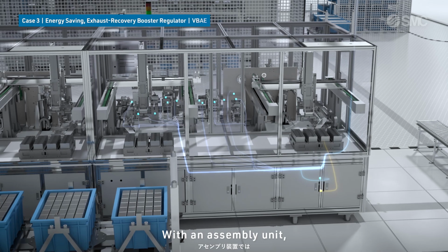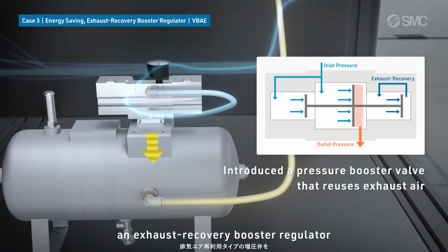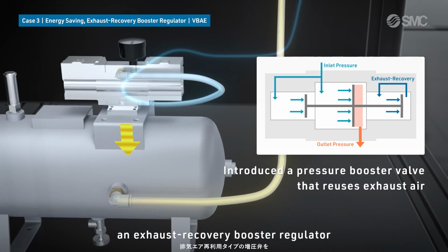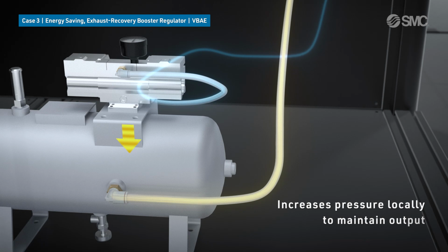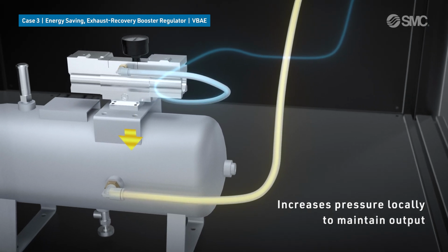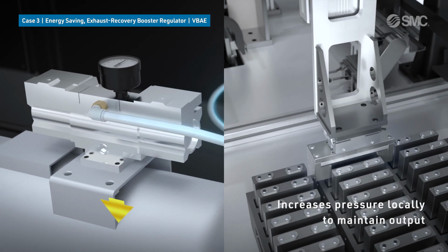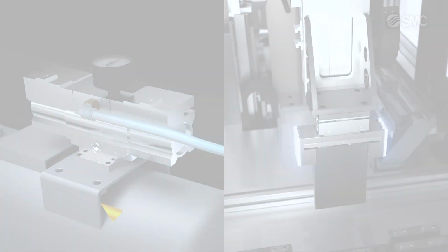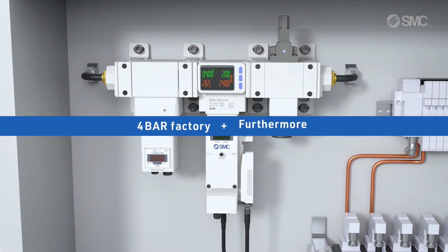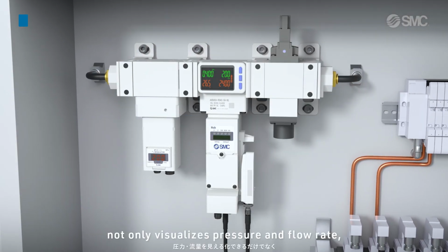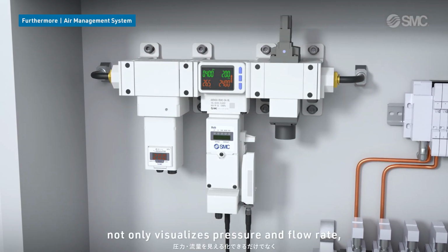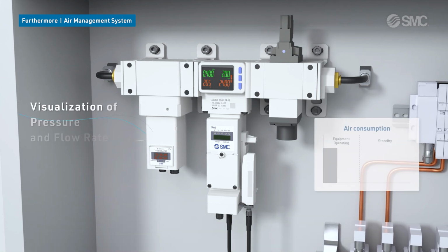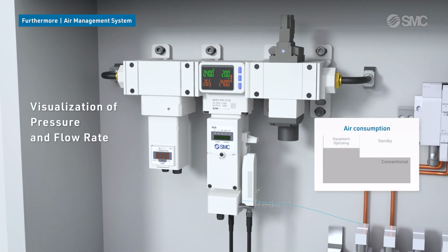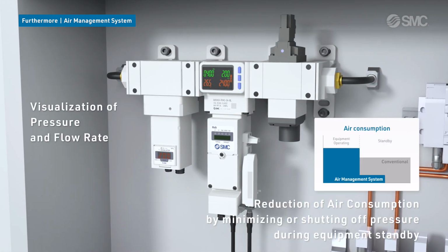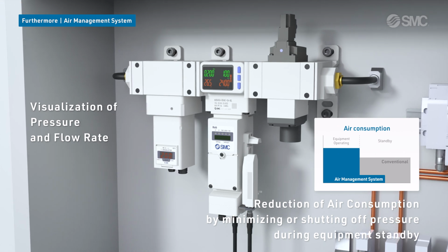With an assembly unit, an exhaust recovery booster regulator can be introduced to locally boost pressure to maintain output. Air management system not only visualizes pressure and flow rate, but also reduces air consumption by minimizing or shutting off pressure during equipment standby.